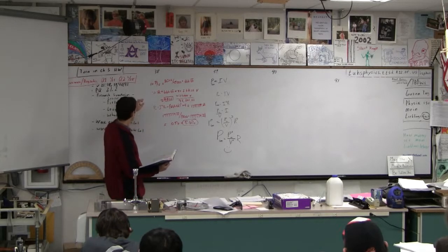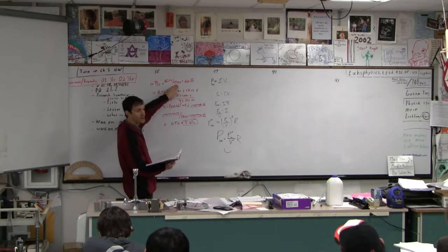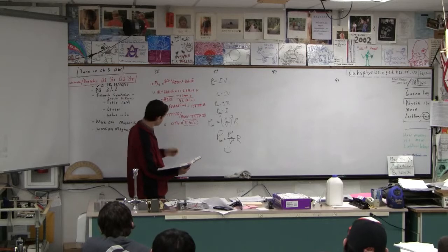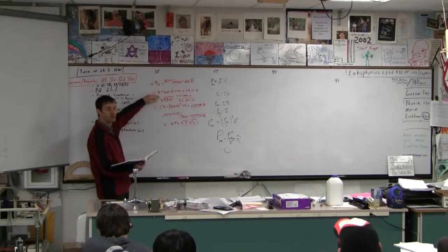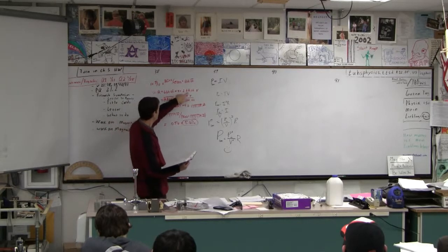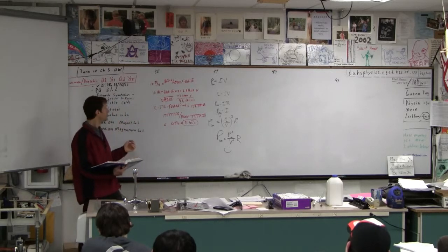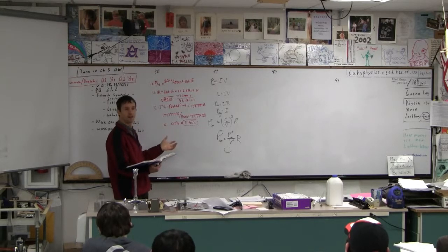And so, I think Anna did this one, right? The first thing she did was she took the power, which is 30 megawatts, divided by 45 kilovolts, and got the current was 666.66666. Okay. Then she figured out that the voltage drop on those lines was 2.6666 kilovolts, right? Okay, that's the voltage drop.